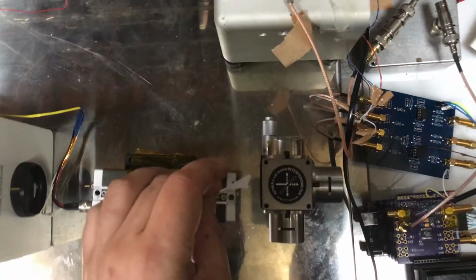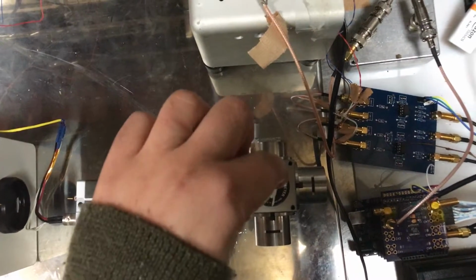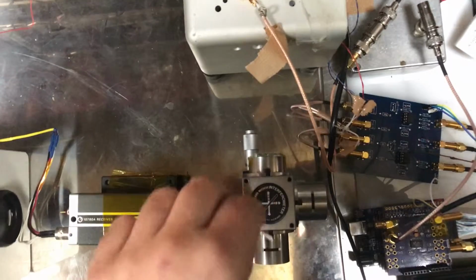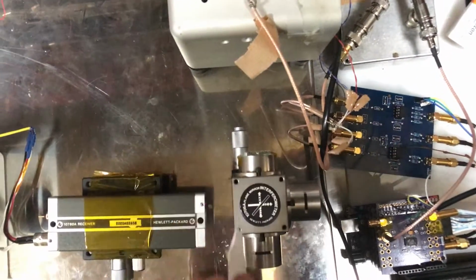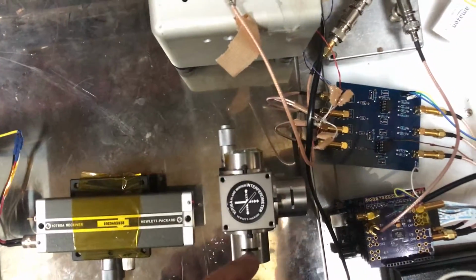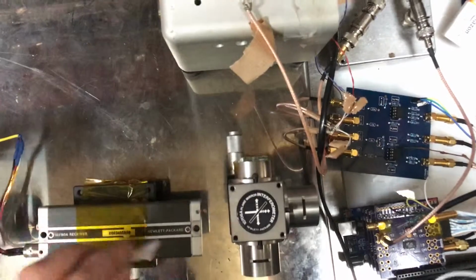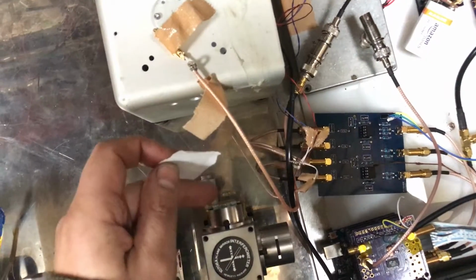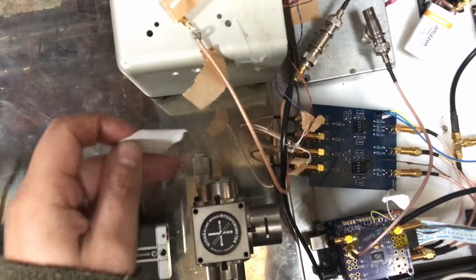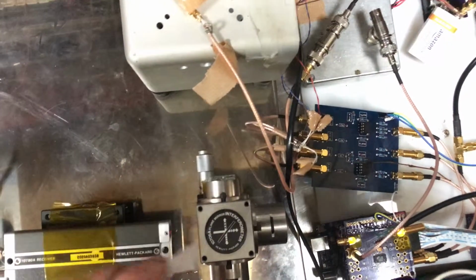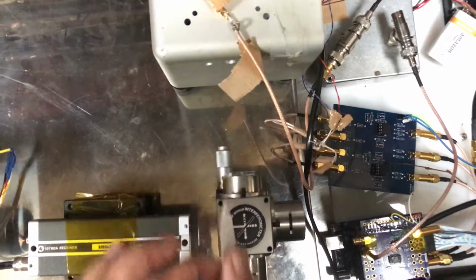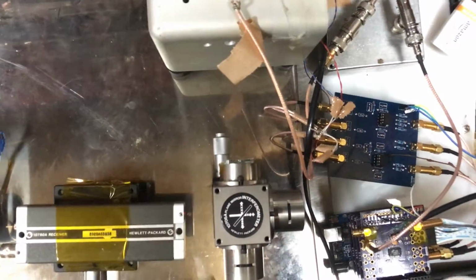you generally read about. You can see the laser is coming in here. It goes into the interferometry block. There's a beam splitter in here, so the measurement beam goes off, and it bounces around, I think, a couple of times, and then it comes out. The reference beam bounces around a couple of times, and then it comes out. So it's just a fixed distance. And then this would be where the measurement beam comes out, and the measurement mirror would be attached to the thing that you're trying to measure the deflections on. And the measurement beam, I think, also bounces back and forth twice, and then comes out the other side.